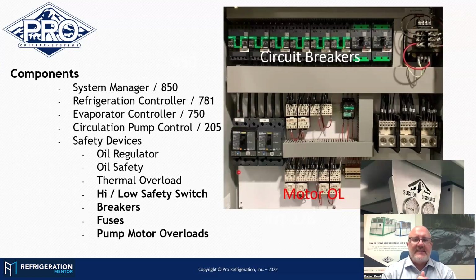That's right. So we get into some of the safety switches, and on the power side, circuit breakers. We've got two control panels. The one that has our main power input, that's where we're going to have circuit breakers. We're going to have contactors, but motor overloads. Now we're just monitoring fluid pump motors, and those overloads are set up with bimetal resistors inside. If they sense too much amperage for too long of a period of time, they're going to trip, and they're set up for a manual reset. There's a reset button right below where my cursor is showing now, the red dot. There's little blue buttons. If they need reset, there is a trip indicator under the plastic piece right here. I know it might be a little hard to see with the size, but I don't typically rely on those very often myself. It takes just a second to hit the blue button, and if you hear a click and it resets, then I know that's my issue, and I've got my amp meter out and I'm checking amperage.